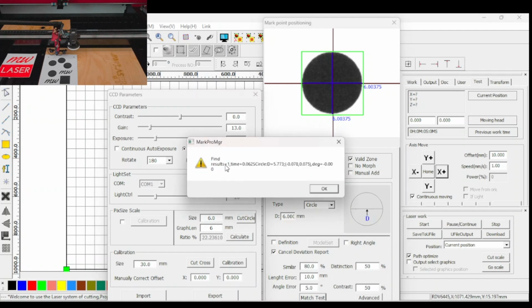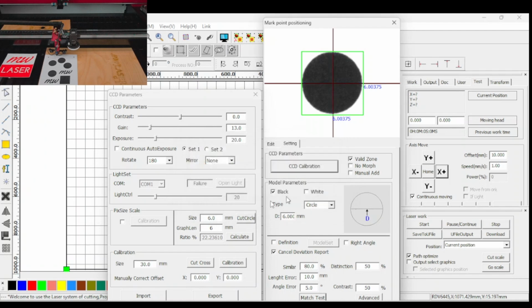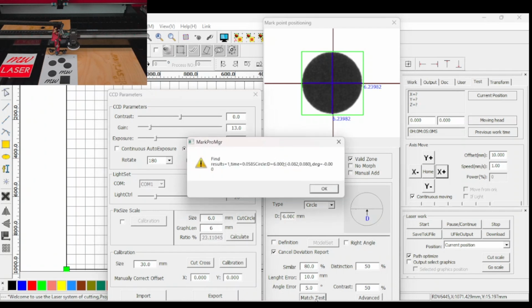It will pop up with this box saying the circle diameter equals 5.773. So we record that and we type in here 5.773. We calculate it and then we do another match test. Now we can see that the circle diameter equals 6. So that's successfully calibrated the size.